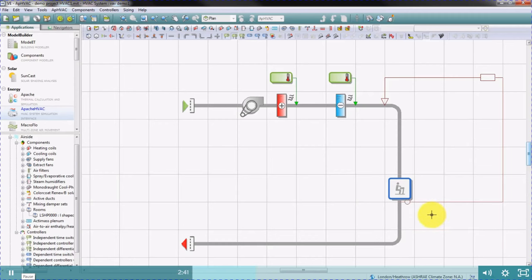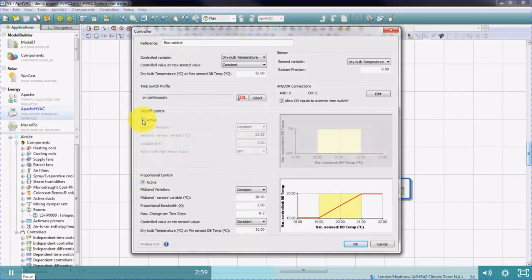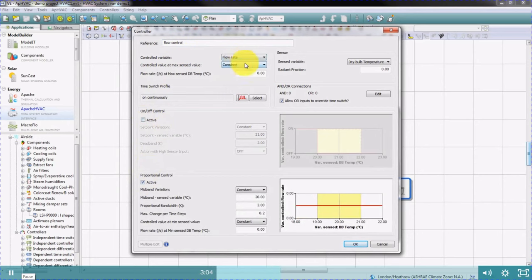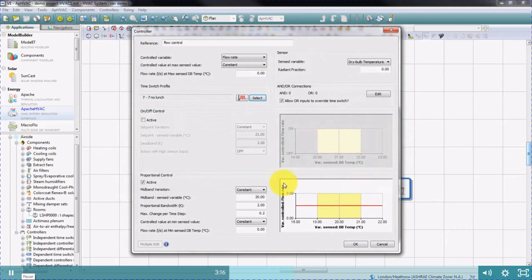We're going to place the sensor position downstream of the room. The controller dialog box will open. We're going to use proportional control in this example. The control variable will be flow rate, the sensed variable will be dry bulb temperature in the room. The control operates on a 7-to-7 profile. Here we will enter the mid-band, i.e. the set point, and the bandwidth.